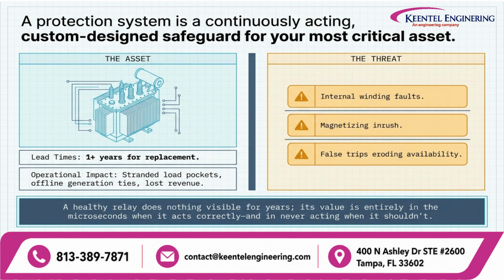This creates the fundamental challenge of transformer protection. The system must be extremely sensitive to real faults, but highly secure against conditions that only look like faults. A healthy relay may appear to do nothing for years, but its real value is measured in the microseconds when it acts correctly, and equally importantly, in the situations when it correctly decides not to act.